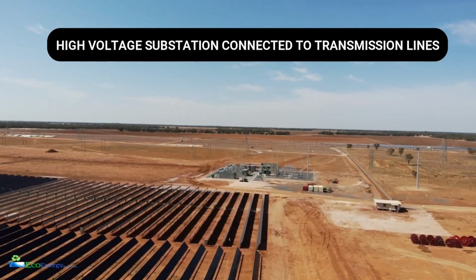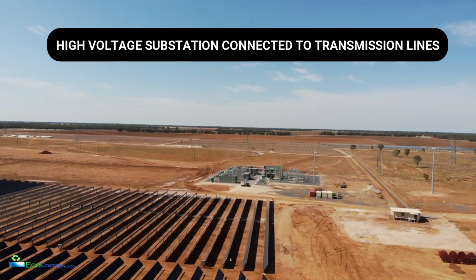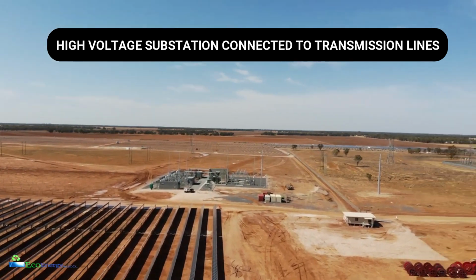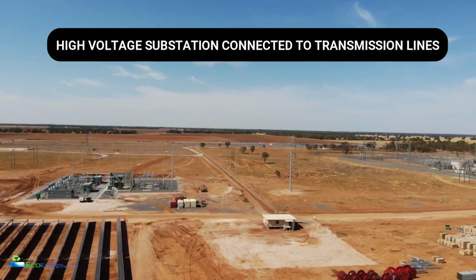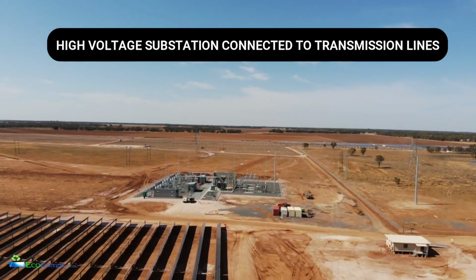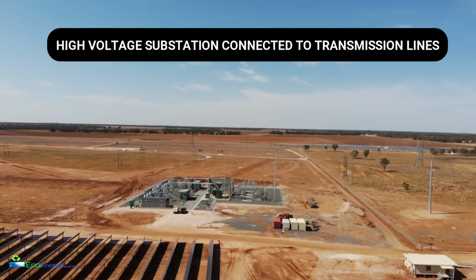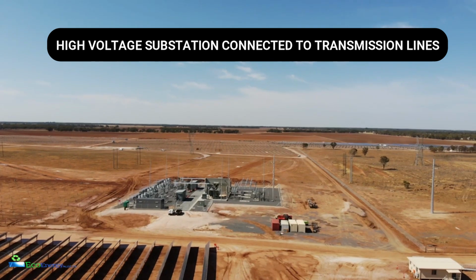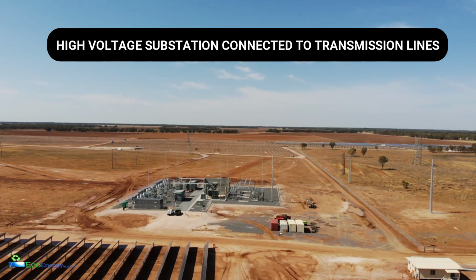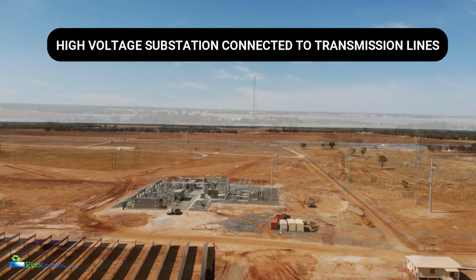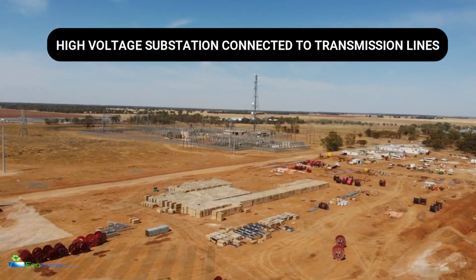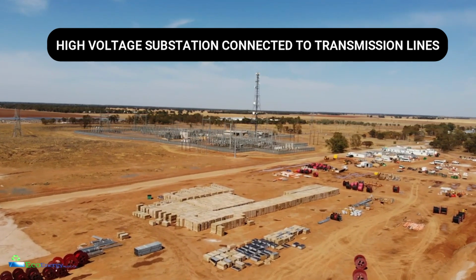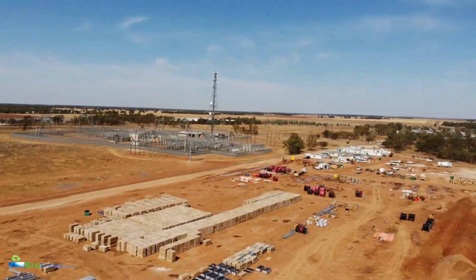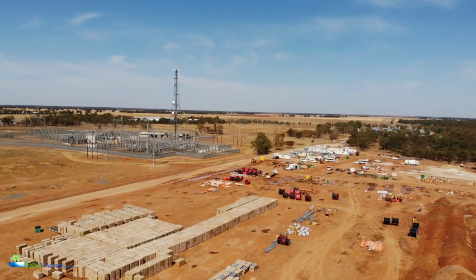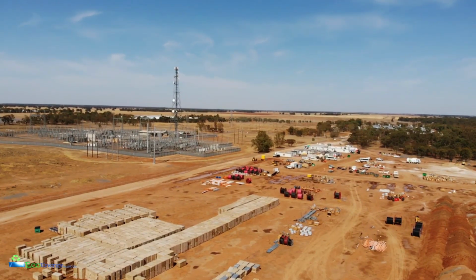Grid connection. The availability, locality, and capacity of the connection to the grid is a major consideration in planning a new solar park and can be a significant contributor to the cost. Most stations are sited within a few kilometers of the suitable grid connection point. This network needs to be capable of absorbing the output of the solar park when operating at its maximum capacity. The project developer will normally have to absorb the cost of providing power lines to this point and making the connection.